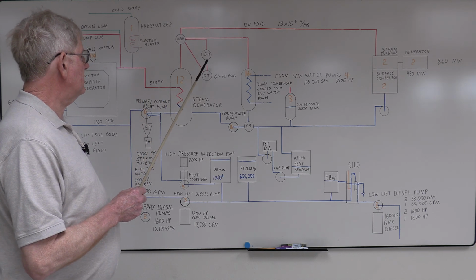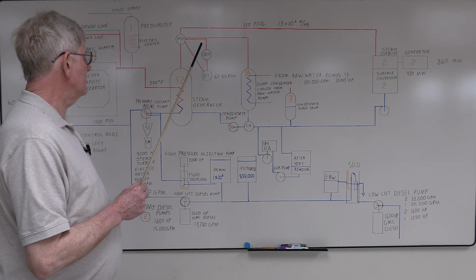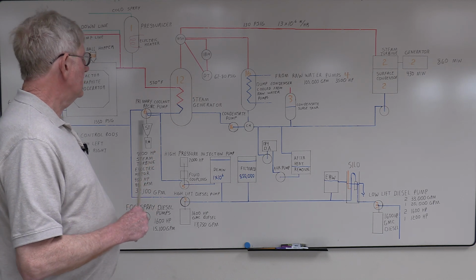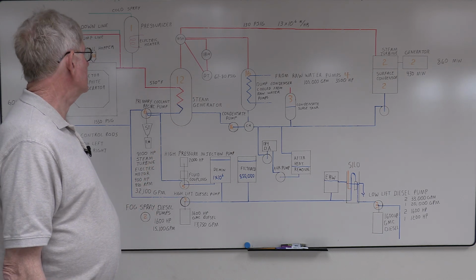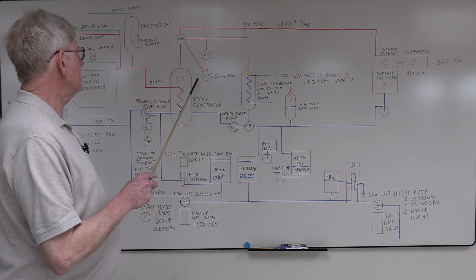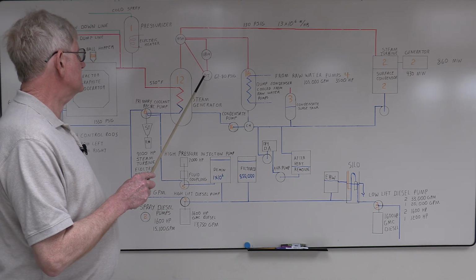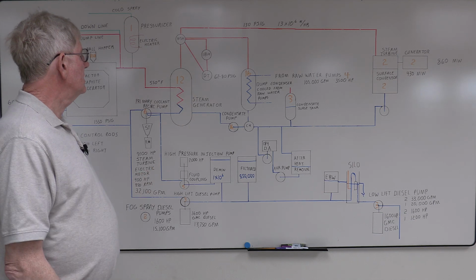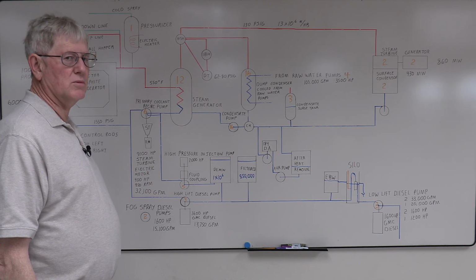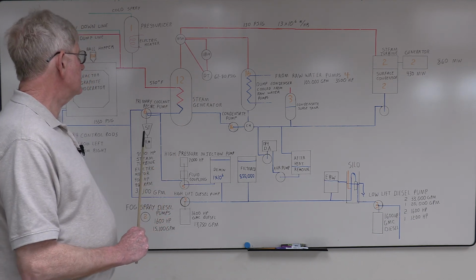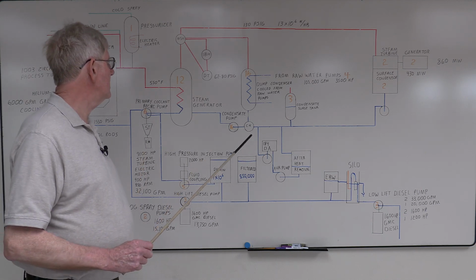If we lost all outside power, that steam turbine generator would power all the B pumps and you'd have a safe shutdown. The drive turbine header was also fed off of this, through pressure reducing valves. Drive turbine header ran around 62, no more than 80 psi. That provided steam to the steam turbine.